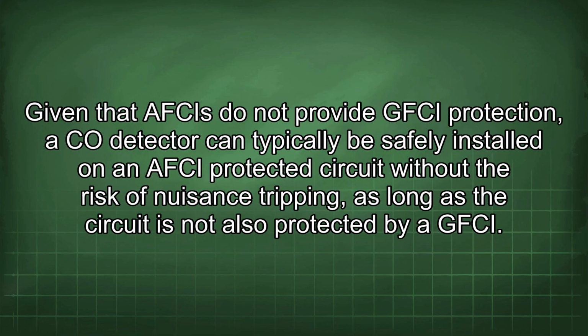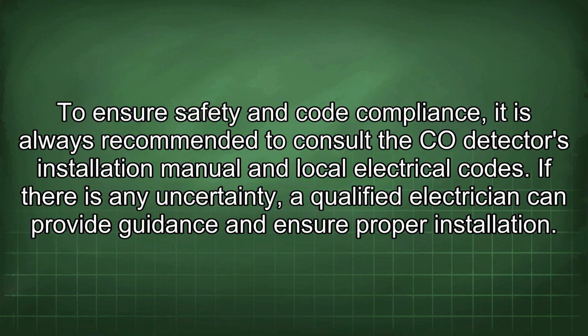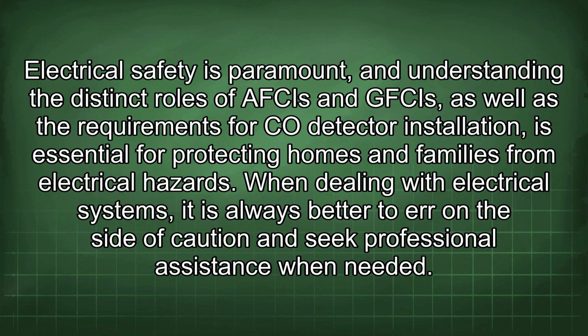Given that AFCIs do not provide GFCI protection, a CO detector can typically be safely installed on an AFCI-protected circuit without the risk of nuisance tripping, as long as the circuit is not also protected by a GFCI. To ensure safety and code compliance, it is always recommended to consult the CO detector's installation manual and local electrical codes. If there is any uncertainty, a qualified electrician can provide guidance and ensure proper installation. Electrical safety is paramount, and understanding the distinct roles of AFCIs and GFCIs, as well as the requirements for CO detector installation, is essential for protecting homes and families from electrical hazards.